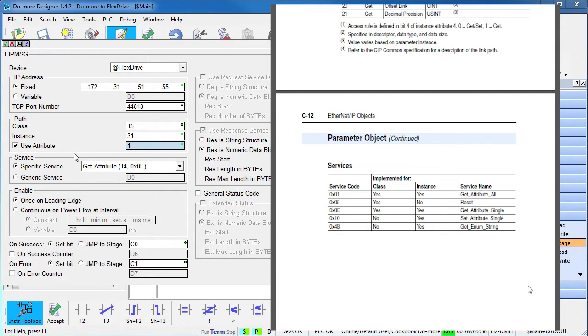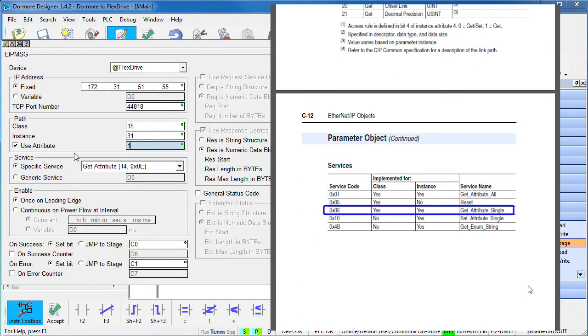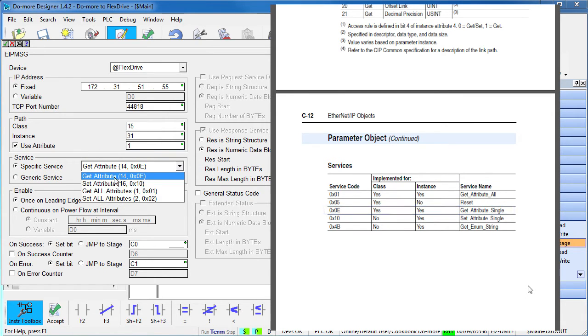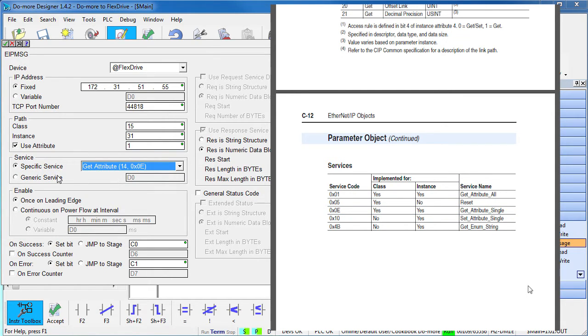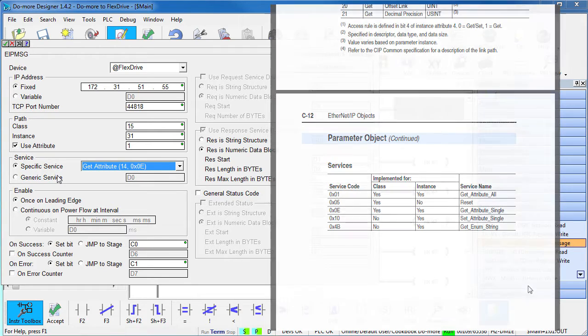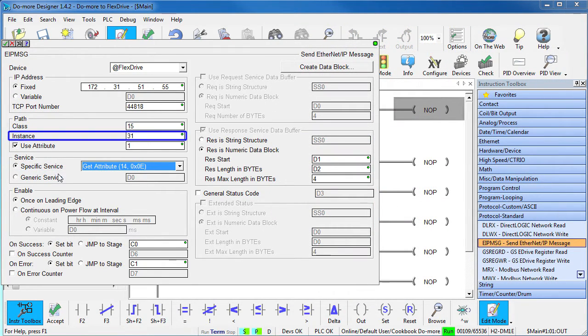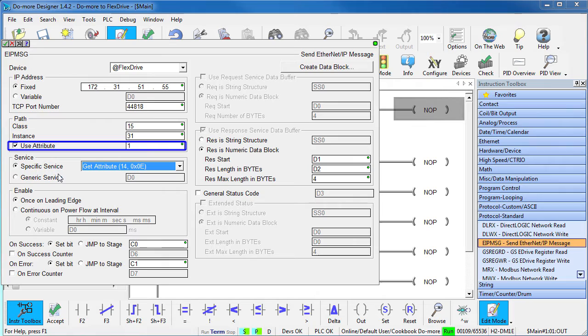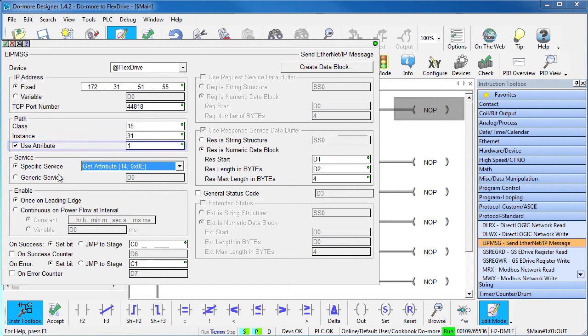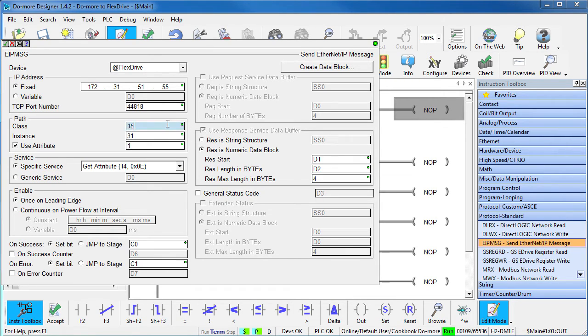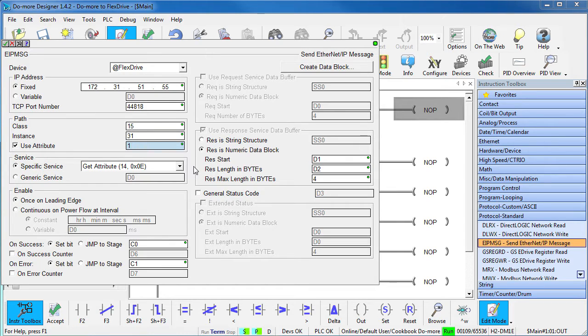This is the format for the services table for this class. We want to get a single attribute, which is a 0E hex or 14 decimal. So we put that one here. And that's all there is to it. You just go to the hardware manual, look up the numbers for the service, the class, the instance and the attribute of that instance that you want and you're done. In this example, we want to get from the parameter class, parameter 31, which is instance 31, and we want to know the nameplate voltage of that instance, which is attribute number 1.